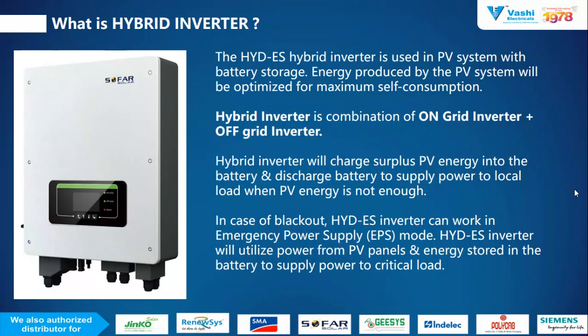So during the EPS mode or emergency power supply mode, when the grid is not available as well as your PV power is not available, in this condition you can easily consider this inverter as a UPS. It means it provides the supply to your critical load, meaning it provides electricity to light, fan, and refrigerator. These are the critical loads. So it is considered like on-grid plus off-grid. Next.